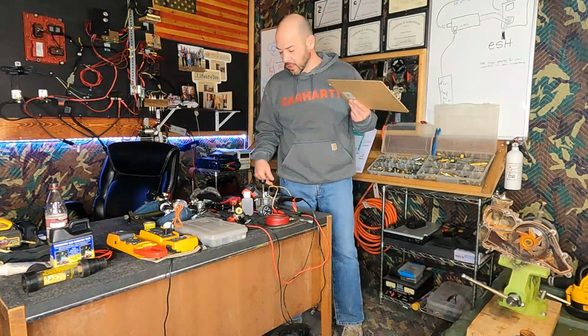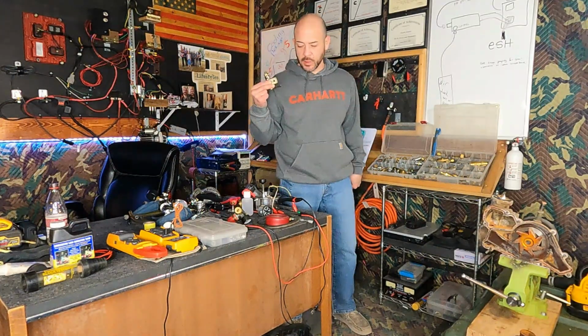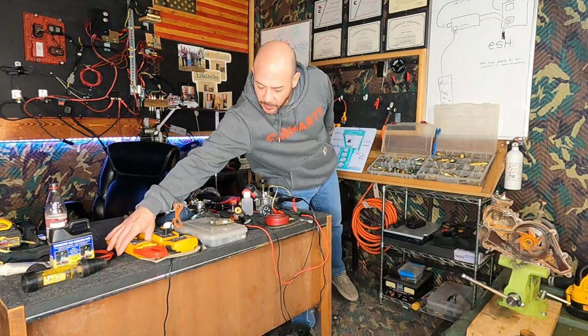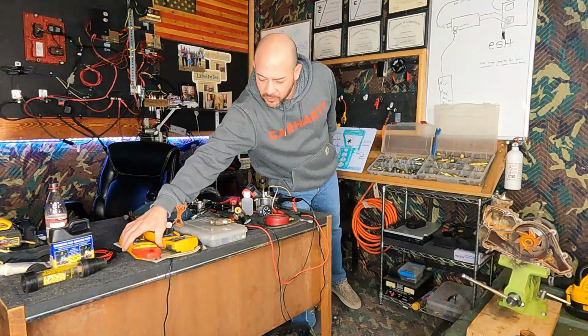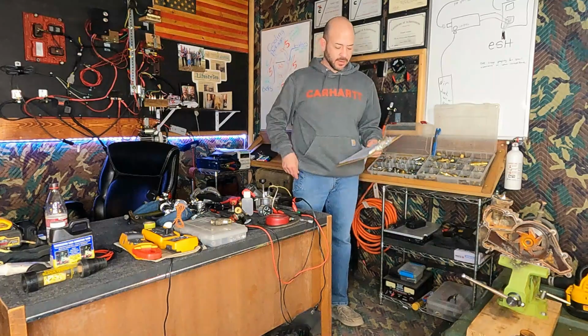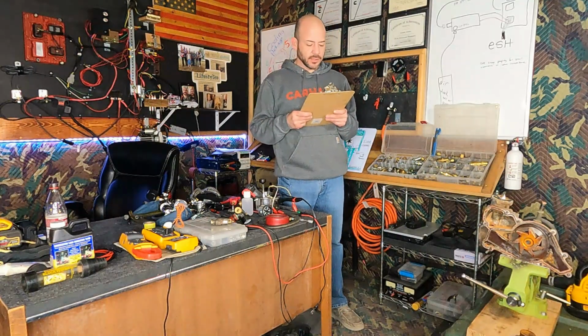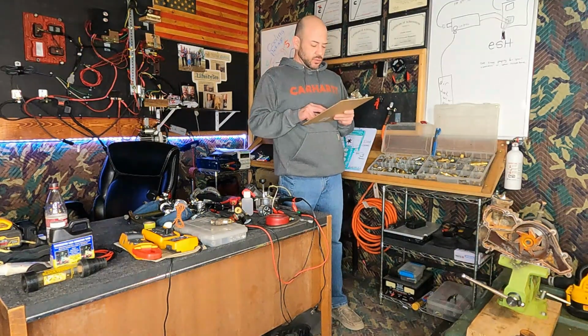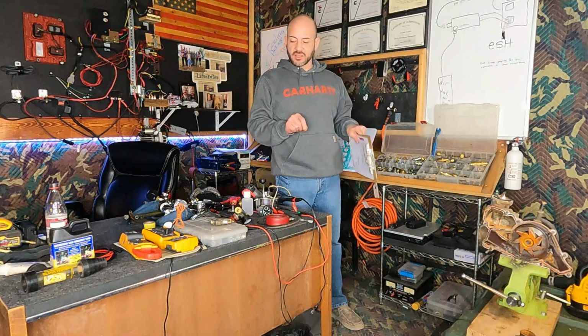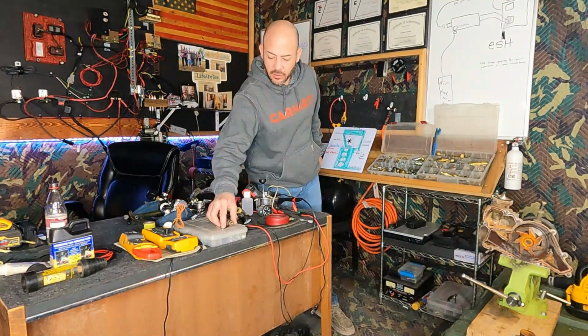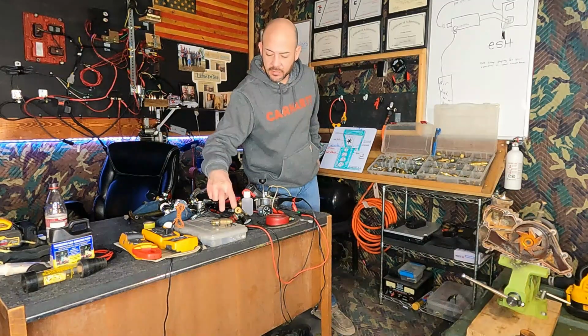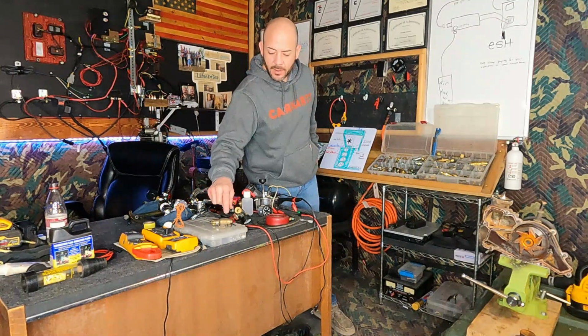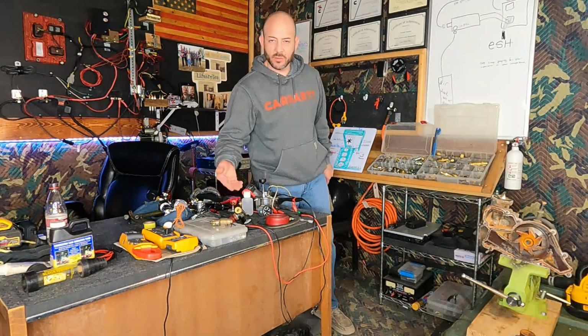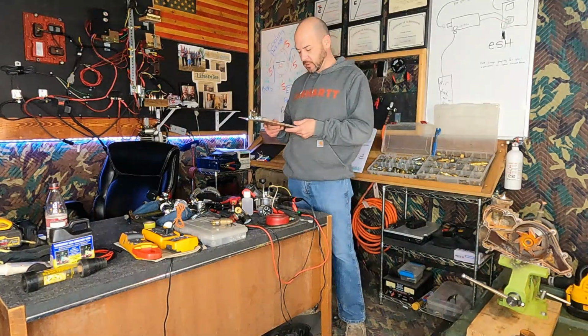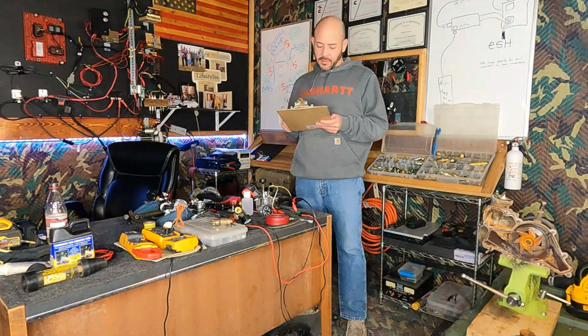Amp draw to the solenoid itself is another quick way to check. I can put my amp clamp over the wire and see how many amps it's pulling, if any, to tell if it's operating or pulling too much. Also, resistance checks across them—putting your multimeter on ohm readings and testing the coil with one lead here and one lead here—it should be within a certain amount of resistance. Check your specs as far as what that is.